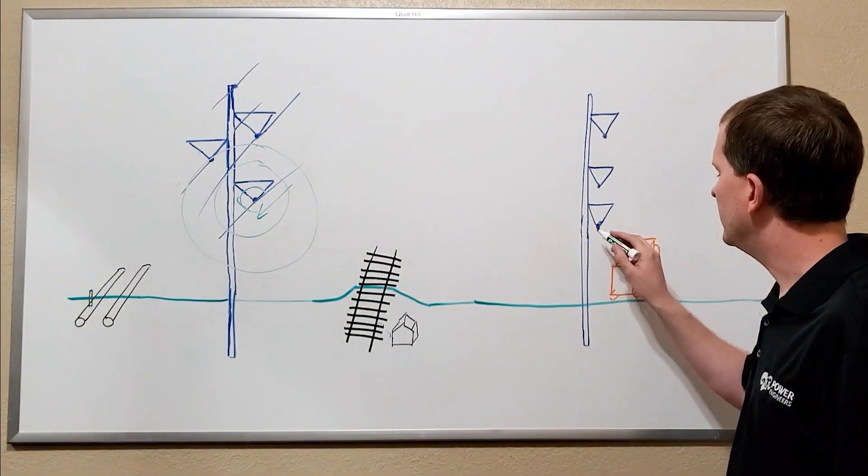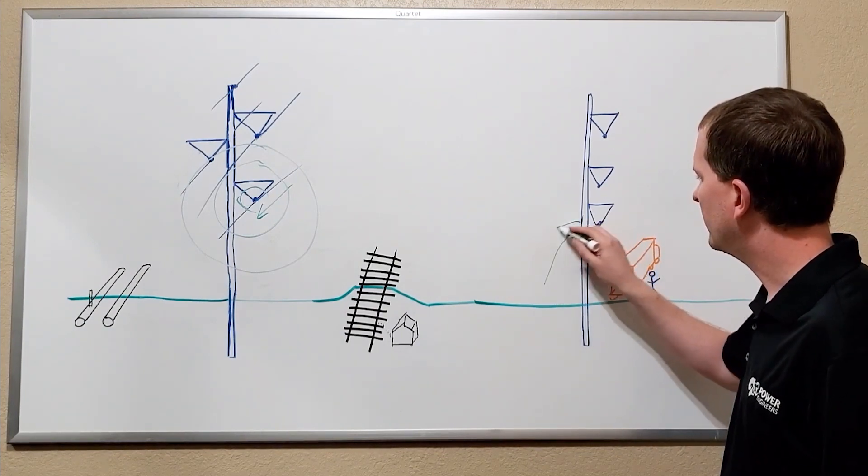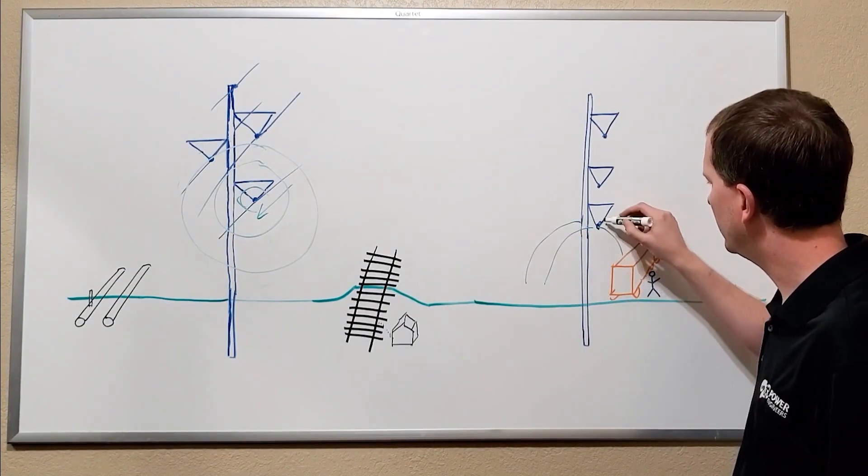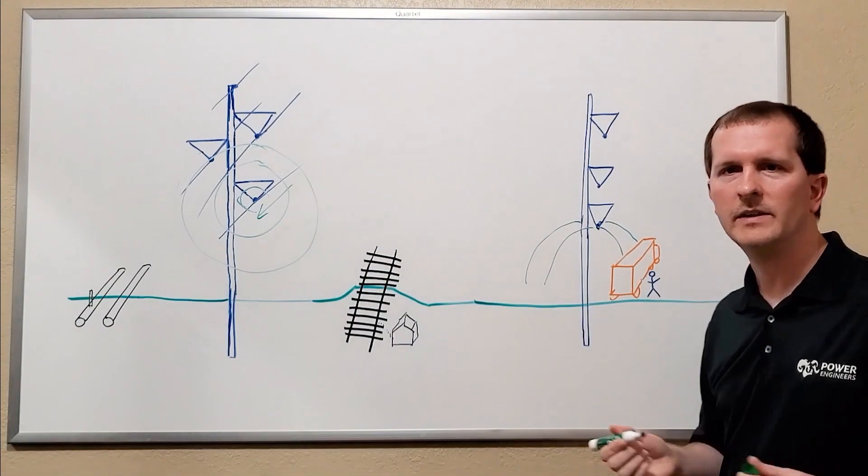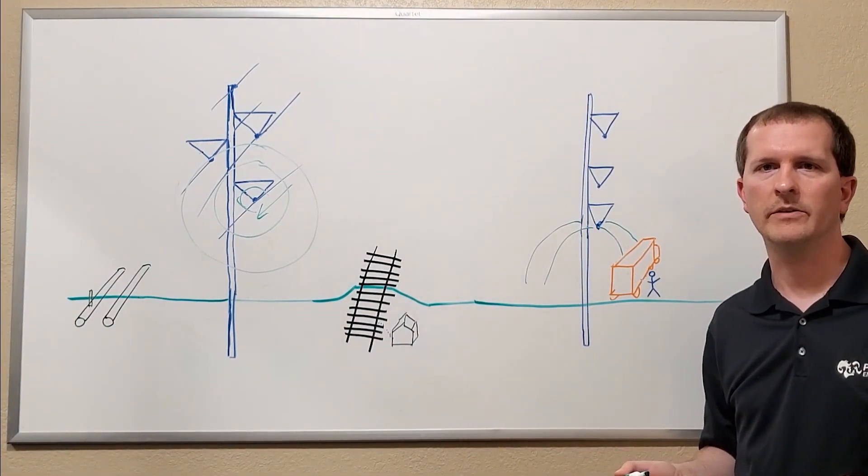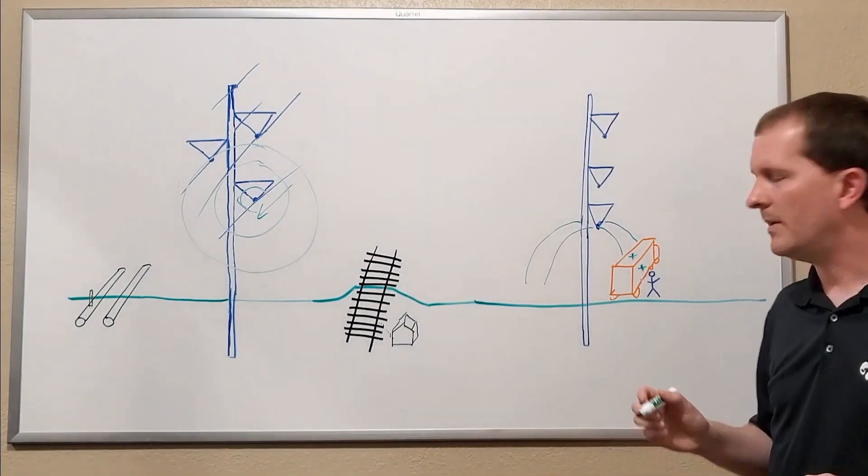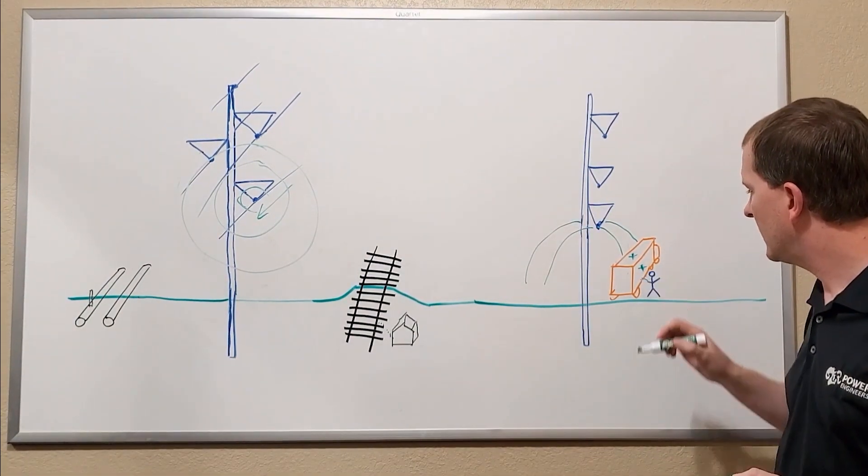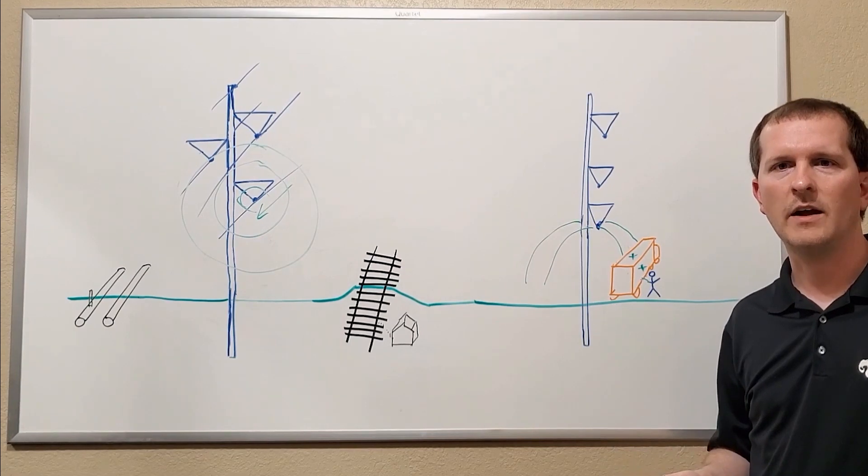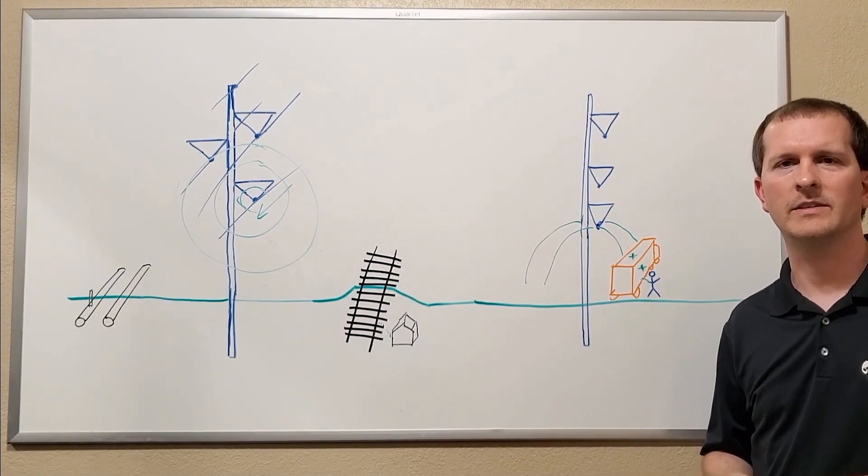The voltage on transmission line generates electric fields that can couple onto large ungrounded objects. One example is a large truck parked underneath the line, which can build up a charge on it. If an individual comes up and touches the vehicle, they'll be exposed to a shock that's very similar to a static electricity discharge, but can be much greater in certain instances.